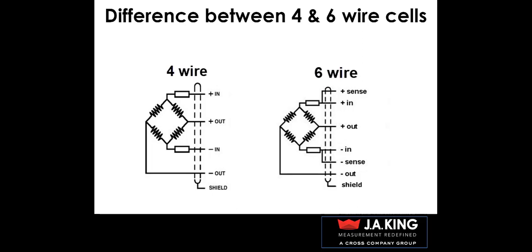The 6-wire load cells use 2 extra wires known as sense or reference wires. These sense wires connect to the excitation wires at the load cell. This will compensate for any resistance changes in the wiring to the load cell due to changes in temperature. 6-wire load cells can be cut to length, but 4-wire load cells must never be cut because the excitation lines have internal resistors to help compensate for temperature changes, and cutting the cable will affect the calibration.